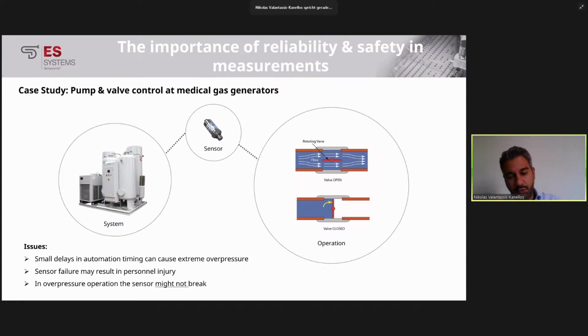While if you are monitoring over the net, let's say, the performance of the equipment, which is most usually done nowadays, you won't see any issue with the indications of the system. Now, this could be an effect of overpressure inline of the system, and the sensors getting damaged and then giving faulty results and faulty measurements, and therefore the equipment not operating as expected. This can be a really tricky and economically dangerous thing for the operation of a medical gas generator.